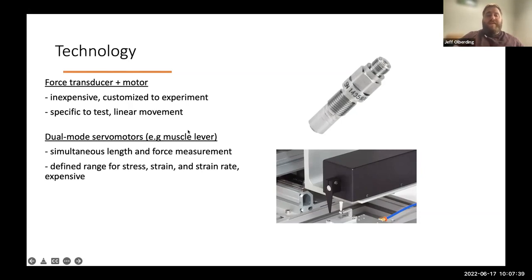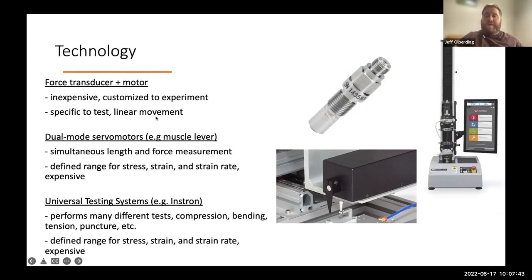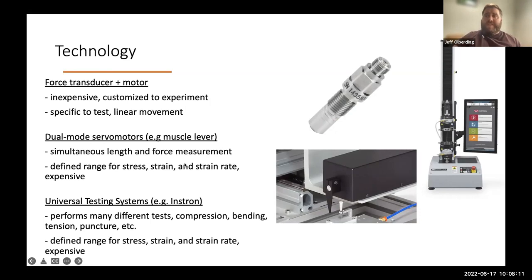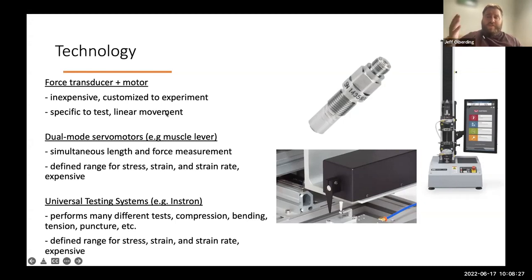On the most sophisticated end of instrumentation, you have things like universal testing platforms — commonly from the manufacturer Instron. These are setups specifically built to perform a number of different tests to measure material properties, including compression, bending, tension, puncture, etc. They're typically set up to be very user-friendly with designed interfaces for running these tests. But they're relatively expensive and also have a defined range of stresses, strains, and strain rates that can be used. Depending on what tissue you're working with and what properties you're interested in, you may want to use one or another of these different approaches.